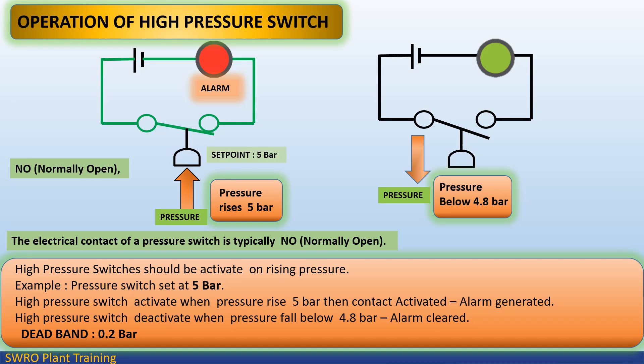Operation of a high pressure switch. High pressure switches should activate on rising pressure. Example: pressure switch set at 5 bar. The high pressure switch activates when pressure rises to 5 bar — contact is activated and alarm is generated. The high pressure switch deactivates when pressure falls below 4.8 bar and the alarm is cleared. Dead band: 0.2 bar. The electrical contact of a pressure switch is typically NO (normally open).